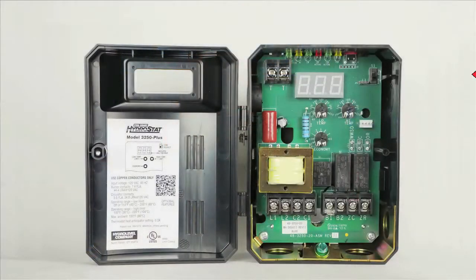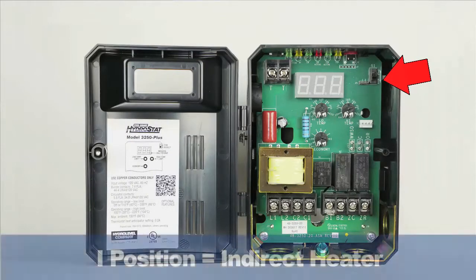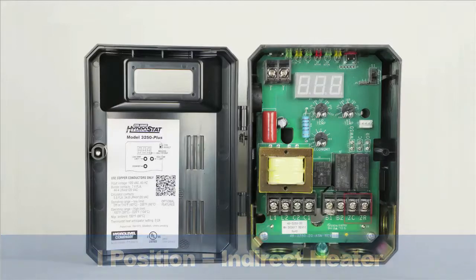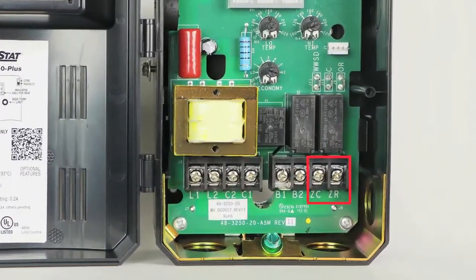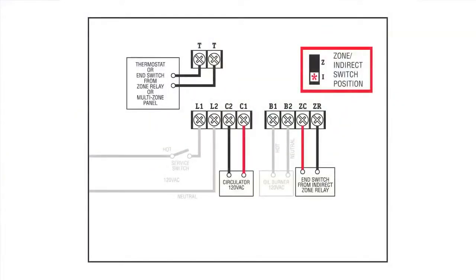When the ZI switch is set to the I position, which refers to indirect heater, the ZR terminal is used to set domestic hot water priority. Whenever there is a call for domestic hot water, the indirect simply returns 120 volts to the ZR terminal to establish the priority cycle. During priority, the heating circulator is de-energized and terminal C1 is off. The economy override bypasses the economy feature and the burner will run to the high limit set point. Any call from the indirect water heater will get priority over zone heating for up to 45 minutes.